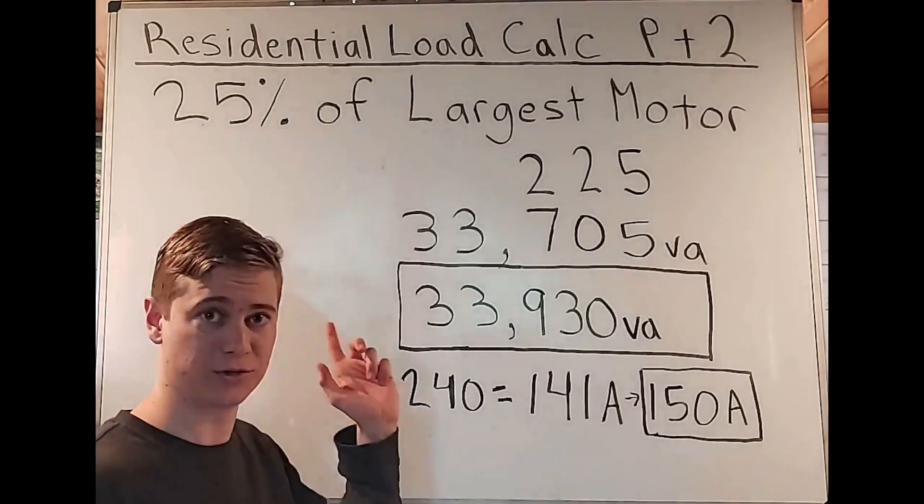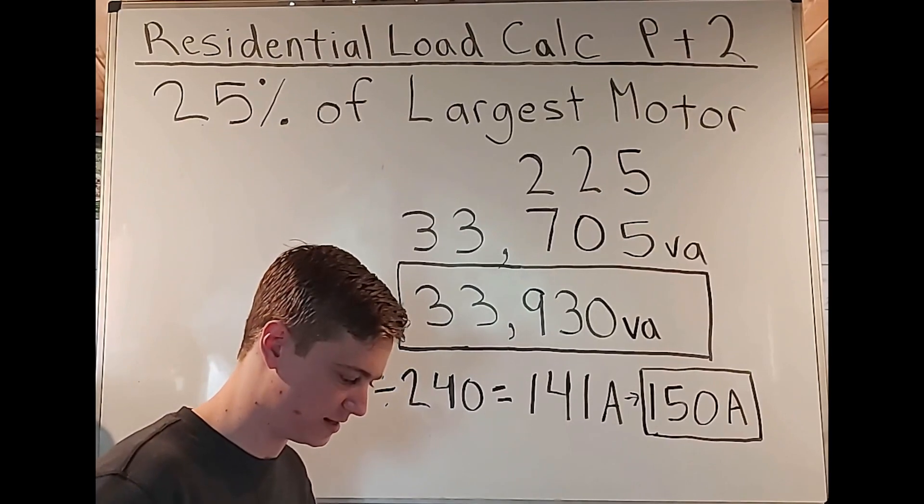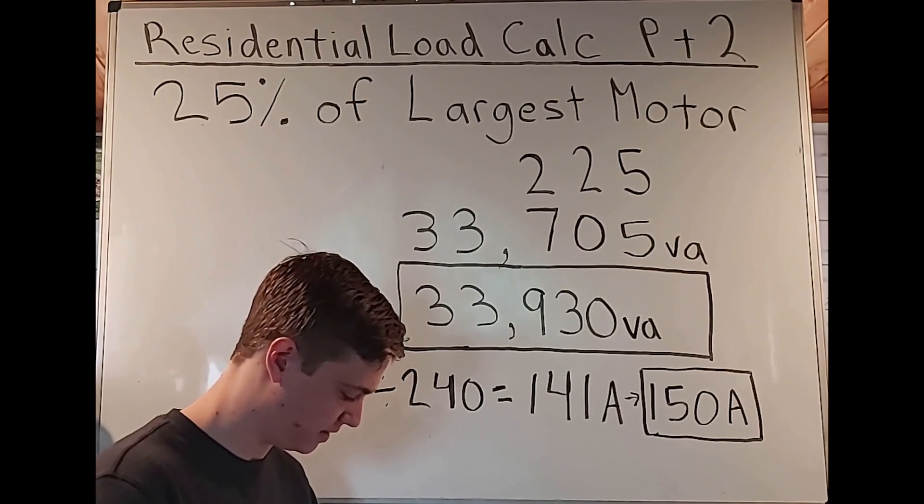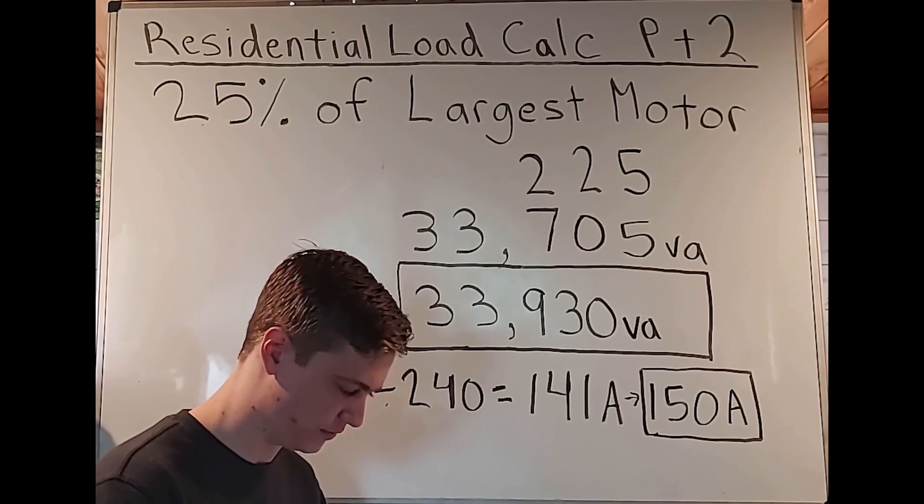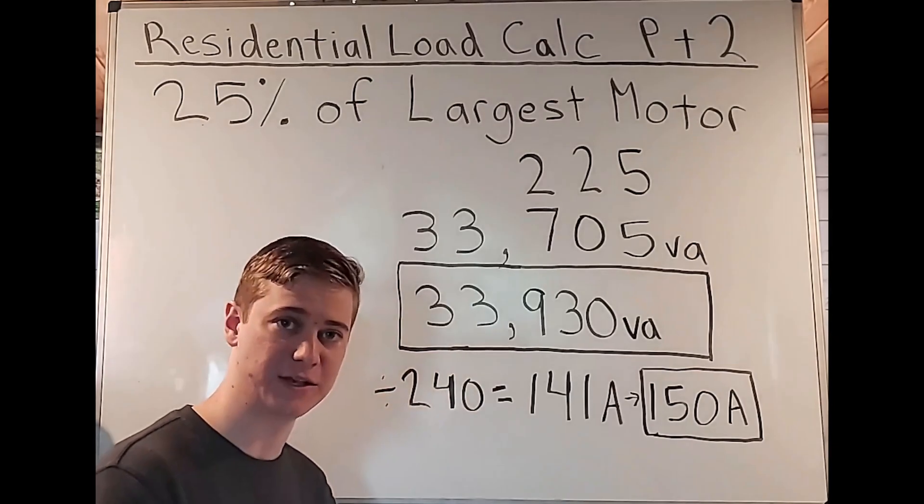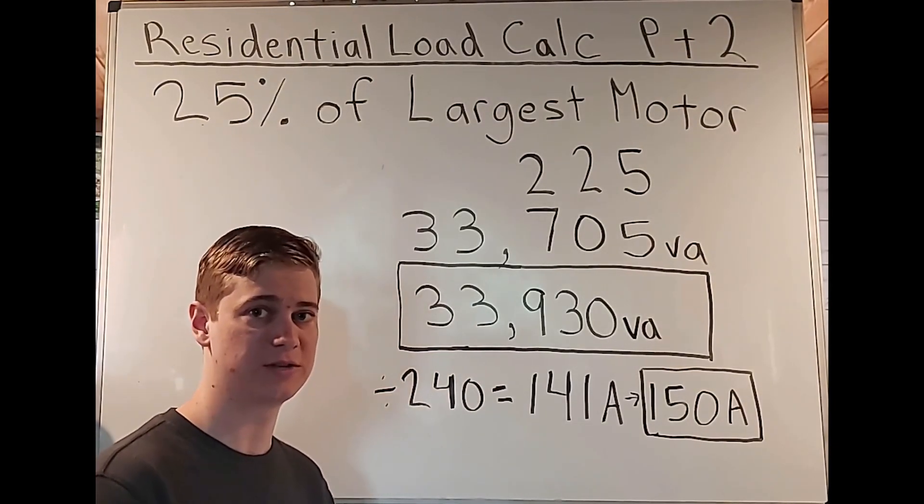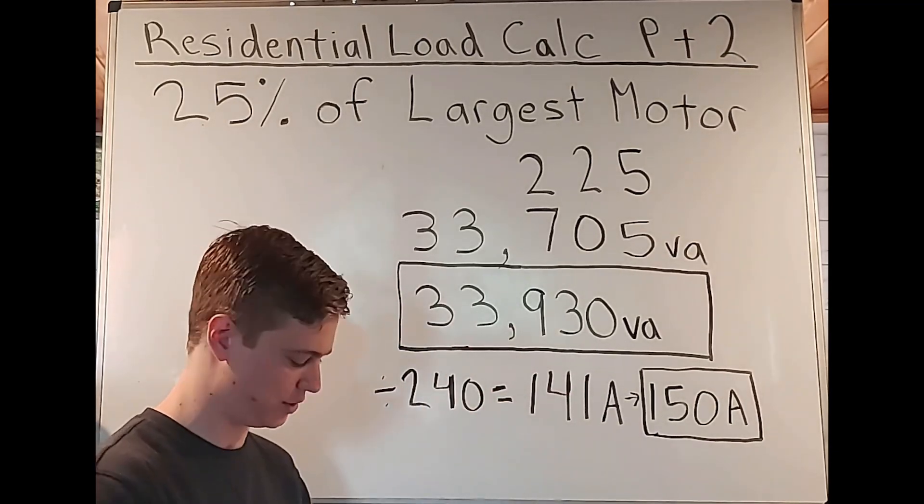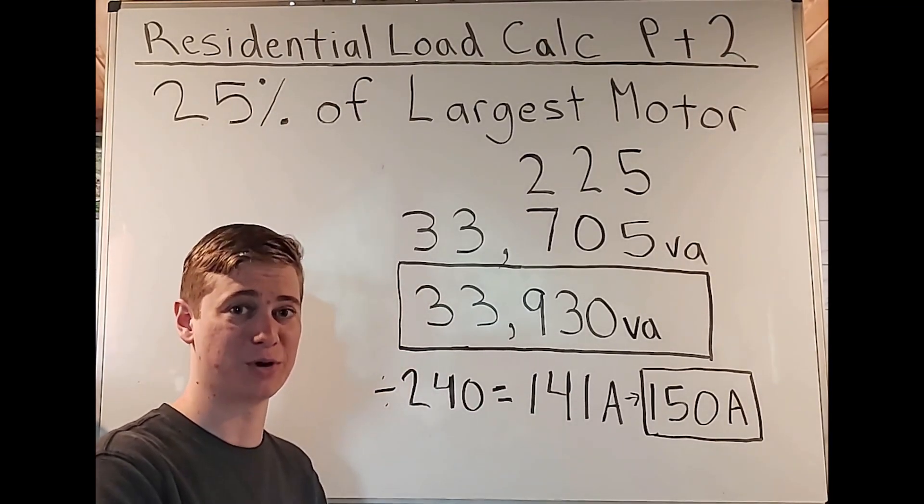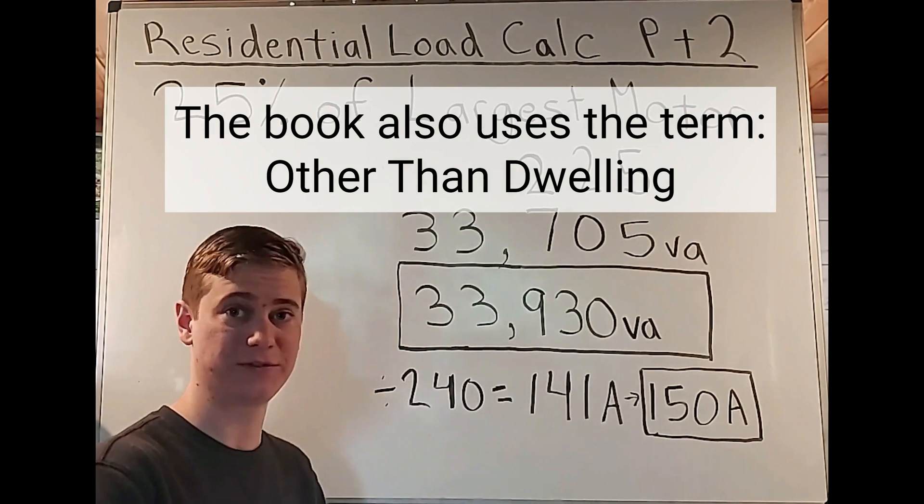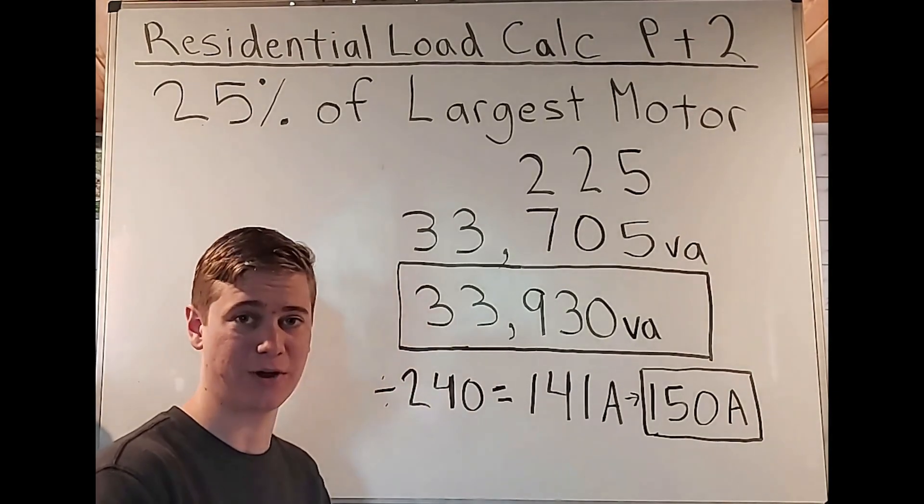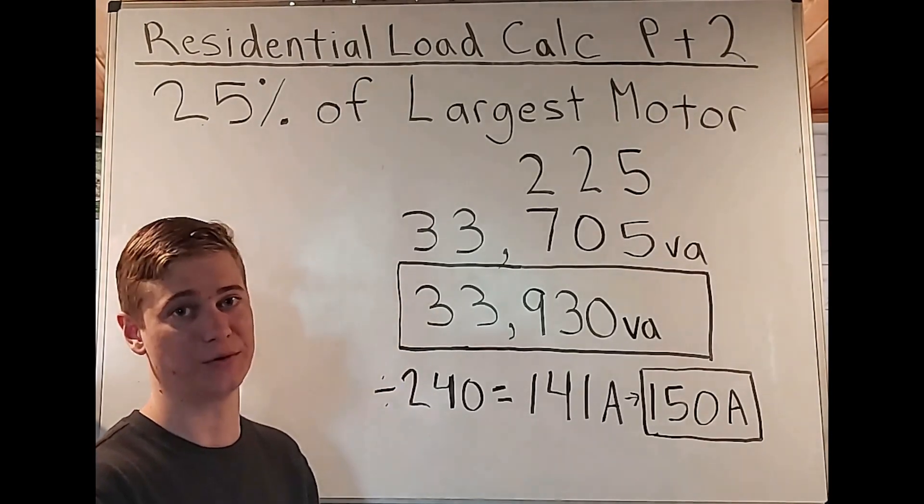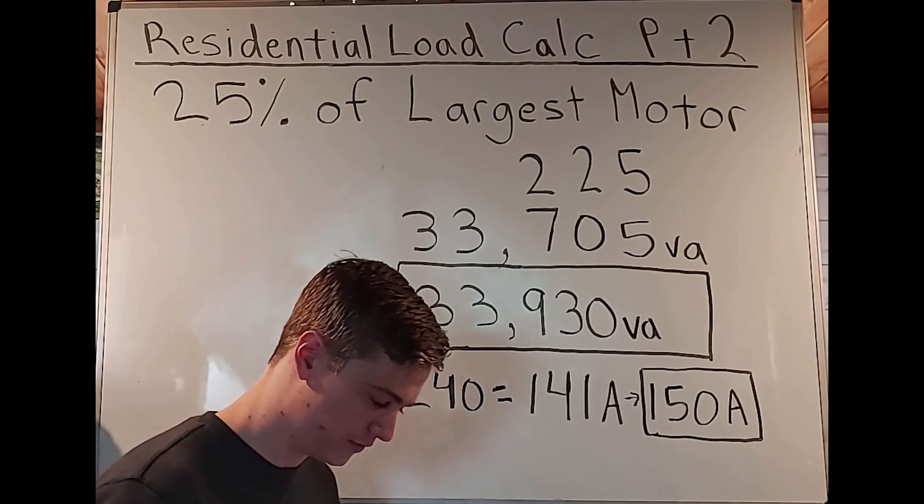Now when we're thinking about residential here, we're not going to be using table 310.16. That does tell us the ampacity of conductors. But if we go back to article 310.12, single phase dwelling services and feeders. So we see single phase, in other words, residential, you got to know some things in the code book when they're talking about houses, multifamily duplex or single, they're going to use the word dwelling. And if they're talking about commercial, which is not a dwelling, what you're often going to find is non dwelling. And along with that, you're often going to have single phase for your dwellings and you're going to have three phase for your commercial.